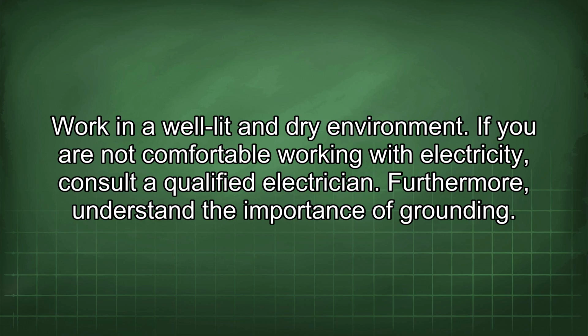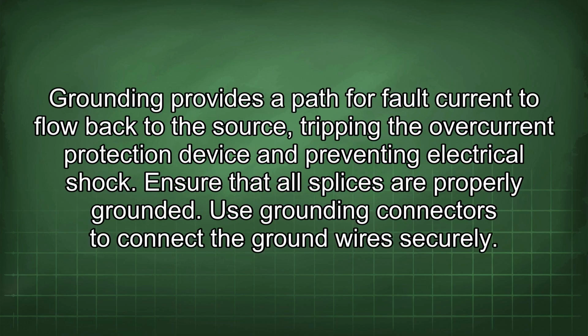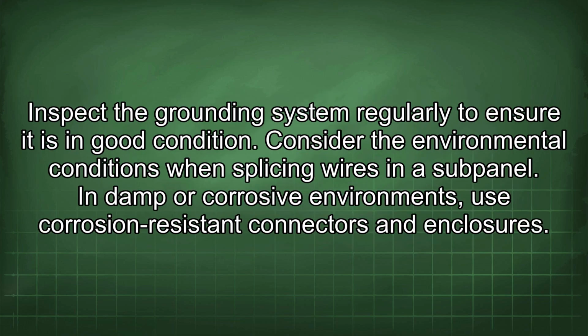Furthermore, understand the importance of grounding. Grounding provides a path for fault current to flow back to the source, tripping the overcurrent protection device and preventing electrical shock. Ensure that all splices are properly grounded. Use grounding connectors to connect the ground wires securely. Inspect the grounding system regularly to ensure it is in good condition. Consider the environmental conditions when splicing wires in the subpanel.